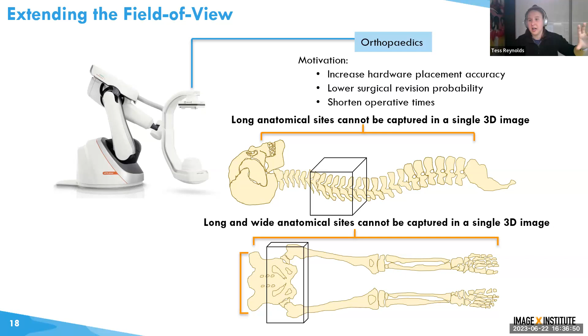In order to do this, we need to think outside the box and think of new ways to actually control and acquire the images with these robotic systems. For the first one, we were just looking to extend the longitudinal field of view. This is the field of view down the table. We can start drawing from acquisitions like a CT that often occur in a helical nature. But we have to take into consideration the restrictions of the system. Our robotic C-arm can't indefinitely rotate in the same direction like a CT can, but it can rotate 400 degrees, so it can go over one full rotation, and then we can bring it back.